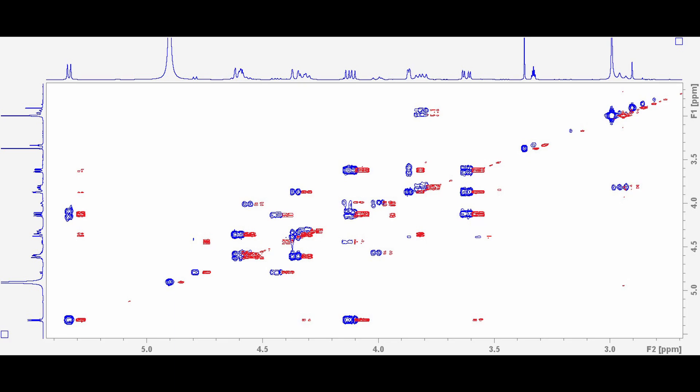So the NUS does provide a way of getting better resolution in an equal time or a shorter time than you would with the regular COSY. And other than that, you may actually get a few extra peaks in the NUS because we are acquiring more increments. That does improve the signal to noise a bit as well. And since we acquire a 1D proton before we do the COSY, you can look beforehand and decide whether or not you need that extra resolution and whether a NUS is warranted or whether the COSY will give you the information that you need.